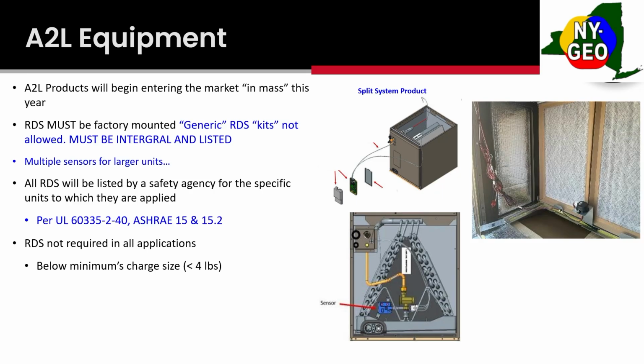And again, the RDS must come built into the unit. It must be integral and listed with the unit. You can't use a third-party RDS. You can't use whatever you want. You have to use what comes with the equipment. A big thing is RDS is not required for any charge below 4 pounds. And this is your releasable charge, a lot different from your full charge. So you have different circuits. You've got to look at a single circuit. Your first point of failure is what they're going to look at here.